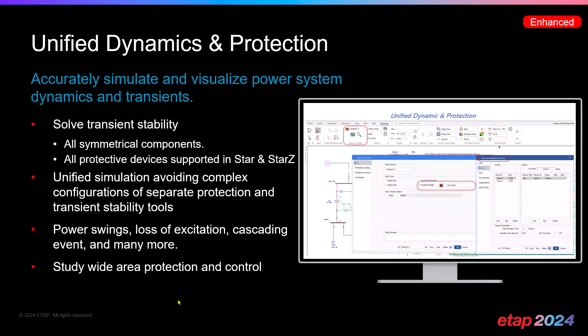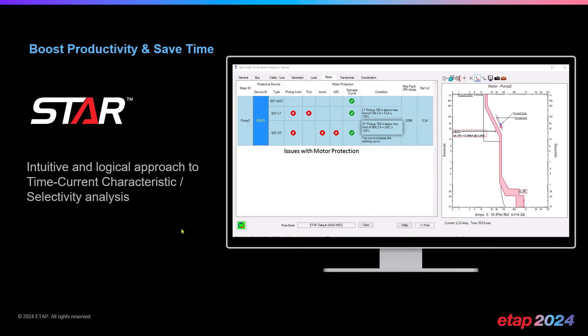Of course, ETAP Star is our module that we use for automatic evaluation of protective device coordination. And of course, it can also be used in a manual fashion when you're not using the auto evaluation to intuitively create your time current characteristic curves and perform your protection coordination and selectivity accordingly. Of course, when Star is combined with AutoStar, which does the automated evaluation, you unlock the full power of protection and coordination by allowing ETAP to assess the protection and coordination or selectivity capabilities within your system, pinpoint the issues, especially in a meshed system, make corrections, and quickly evaluate once again whether your changes solved the protection or coordination challenges within that particular system.